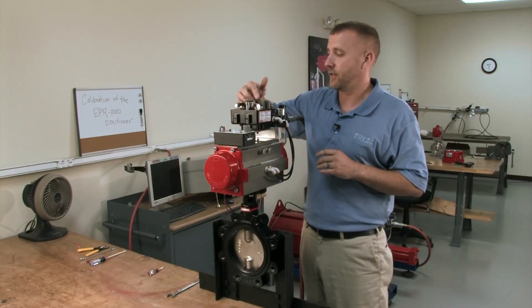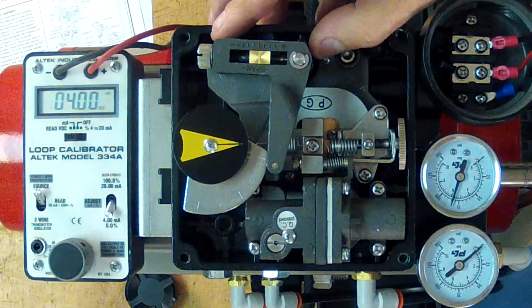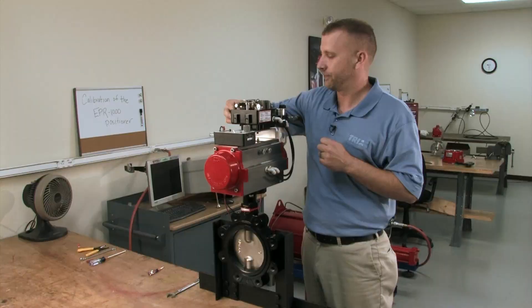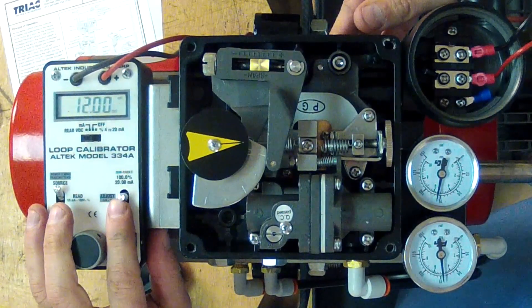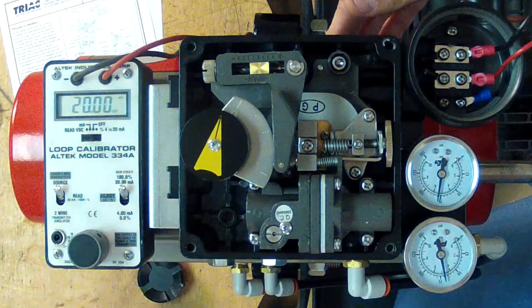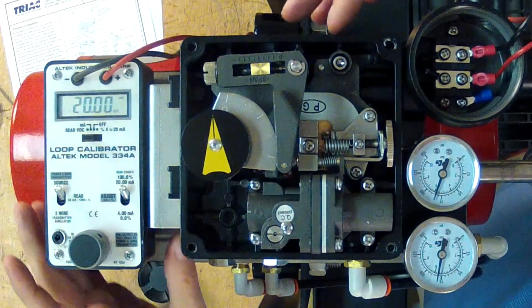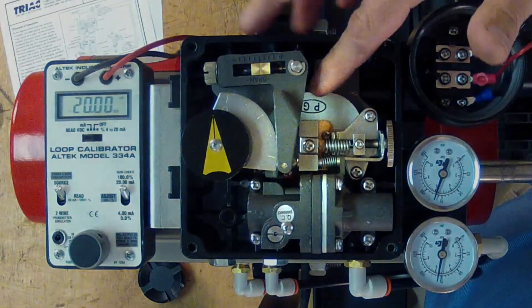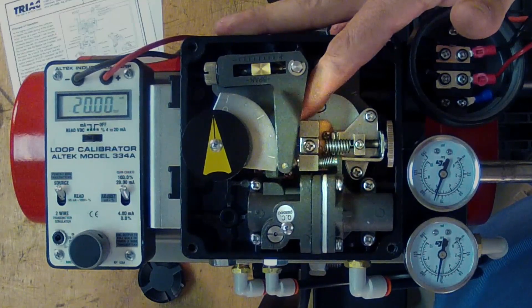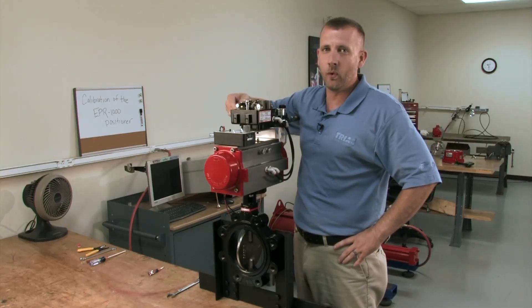One other thing about this positioner is your zero and your span are interactive. That means if you adjust one, you typically have to adjust the other. Now, we're going to run to the 20 milliamp position. And one way to check for your full open in your 20 milliamp position is your counterweight here. You can pull towards you and if you don't hear any air bleed off, that means your actuator and positioner are in the full open position.